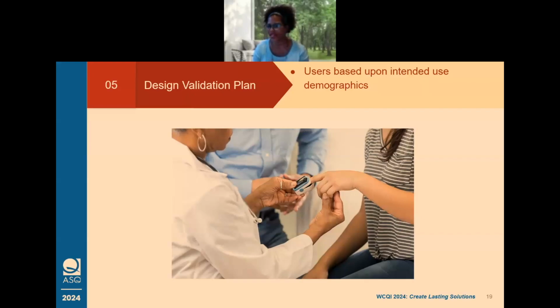So the design validation planning document should outline the processes needed to achieve the intended use. And I'm going to quote the FDA: the performance characteristics that are to be assessed should be identified, and validation methods and acceptance criteria should be established. Straight out of the FDA guidance document. So design validation planning should ensure that outputs from the human factors summative studies and clinical investigations are all tied to the risk management process, and they're evaluated under this stage of development.